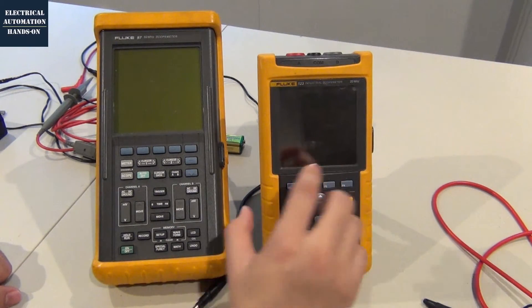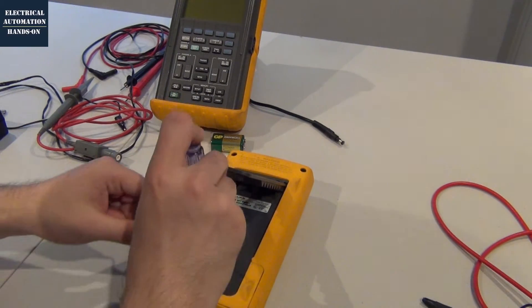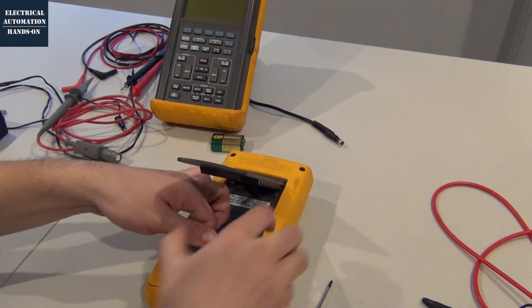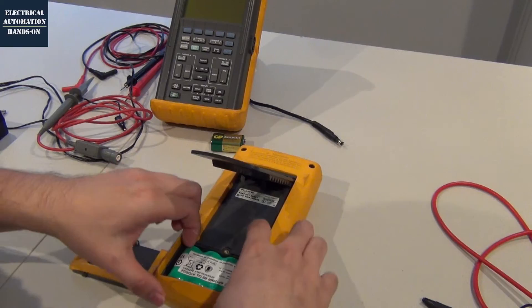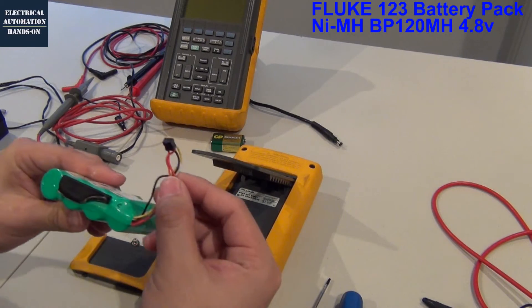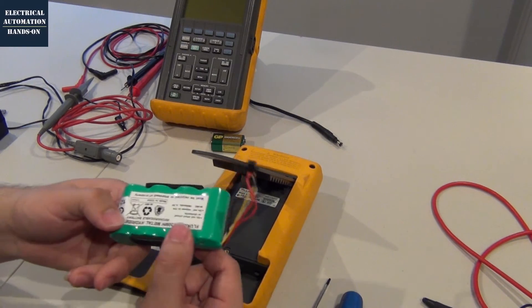And then let me flip it over and open the battery case. Let me show what is inside this battery case. To open this battery case, you need a screwdriver — that is a Torx screwdriver. I'm going to open this and take out this battery. So that is a Fluke BP120MH battery. This battery uses this connector to connect to the scope meter.